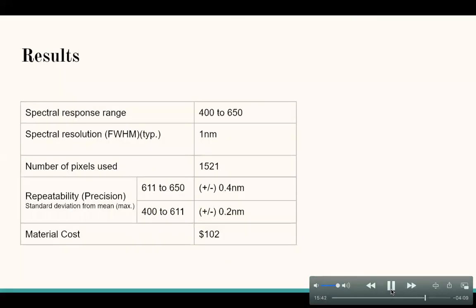Thanks, Christine. Our original objective was to create a visible light spectrometer that spanned the entire visible region from 400 nanometers to 700 nanometers. Unfortunately, we don't have any clear spectrum lines close enough to 700 nanometers for an adequate calibration. As shown previously, the largest fluorescent wavelength used in the calibration is around 611 nanometers. We chose to extend our range up to 650 because we used a red laser in determining the resolution.